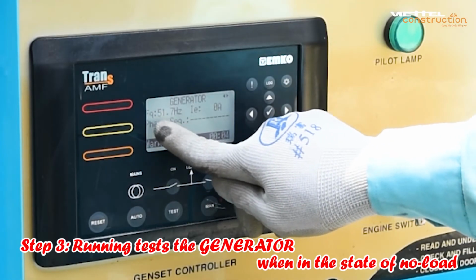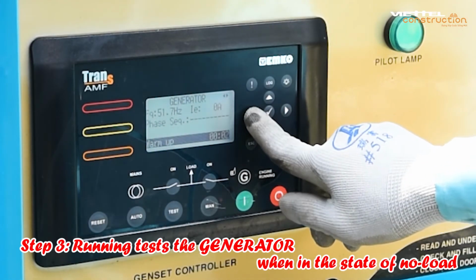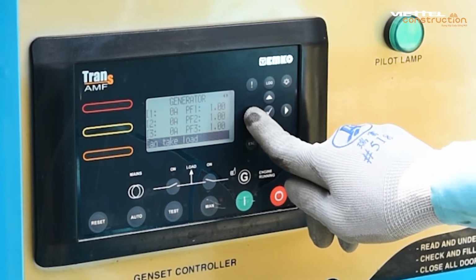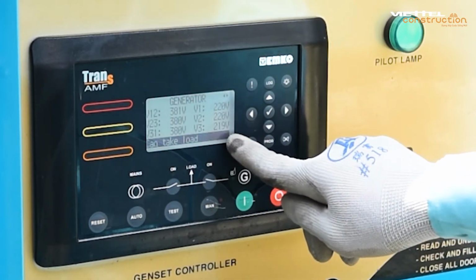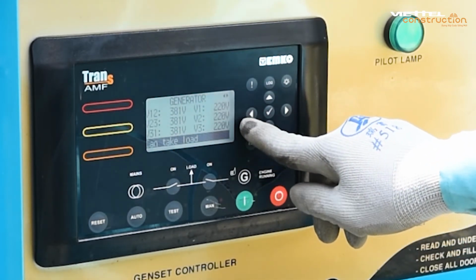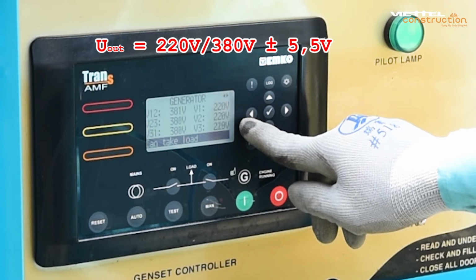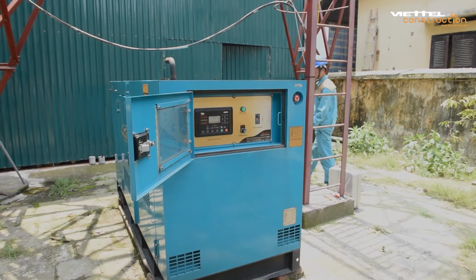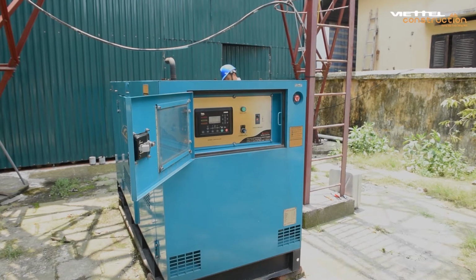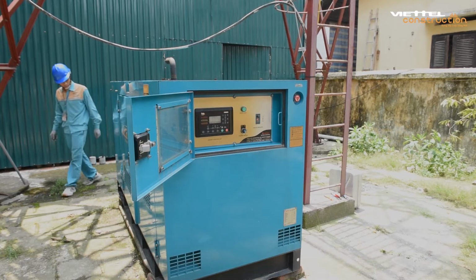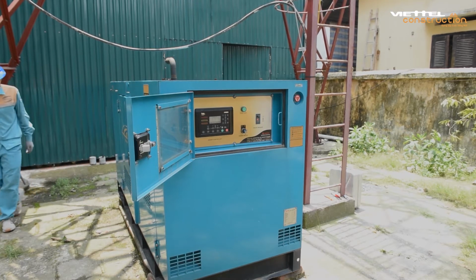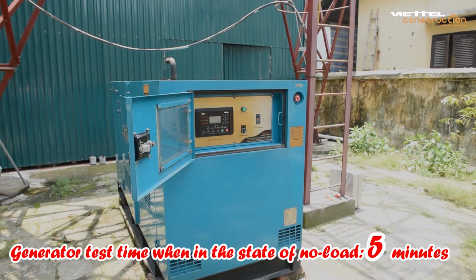Step 3. Running tests the generator when in the state of no load. After the machine runs stably in the state of no load, check the output voltage parameter. Make sure U out equal to 220 volts over 380 volts plus or minus 5.5 volts. Check the whole machine if there is fuel or lubricating oil leak or strange sound, abnormal vibration or not. If there is no problem, then supply power to the device. Generator test time when in the state of no load, 5 minutes.